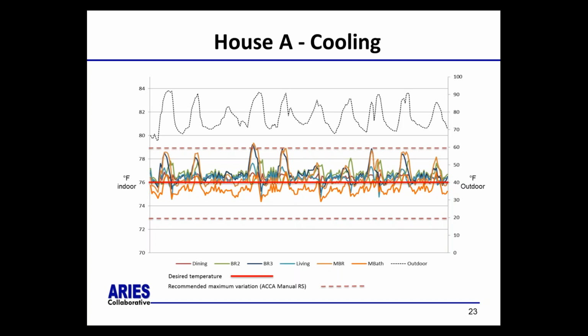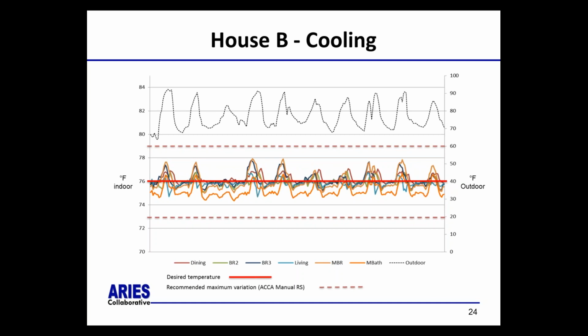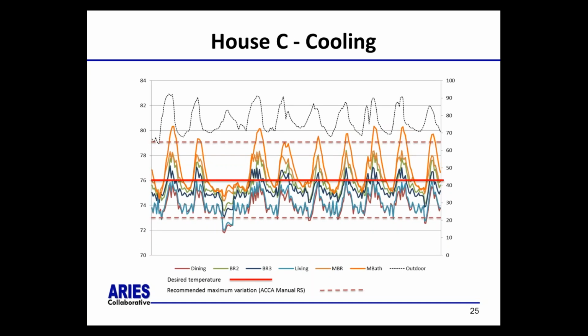So you see House A had variation, but generally within the range of plus or minus 3 degrees of the set point in all the rooms. House B also had a tighter band of temperatures. Thermal envelope is more efficient. The solar gain on the windows is lower in that house, so there were more even temperatures there. House C, wider temperature range as expected, but mostly still within our 6-degree band, with the exception of the master bathroom, which was 2 rooms distant from the source of cooling. So that room got a little bit too warm on the daily peaks. So we're in the ballpark here, but it's not perfect.